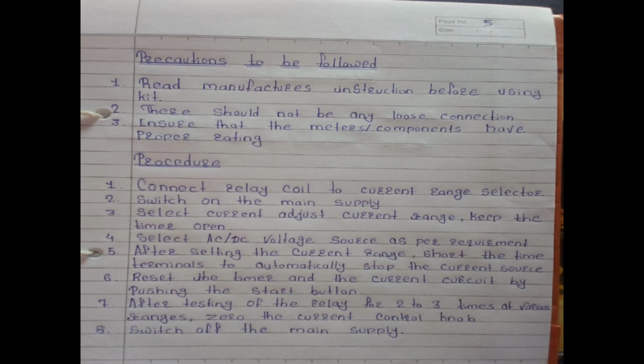Fifth, after setting the current range, short the timer terminals to automatically stop the current source. After testing the relay 2 to 3 times at various ranges, zero the current control knob and switch off the main supply.